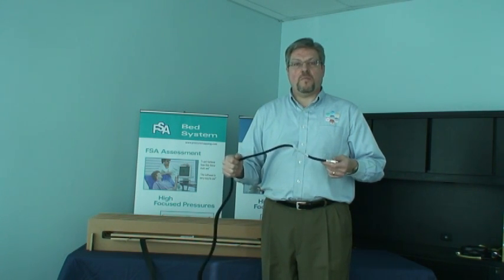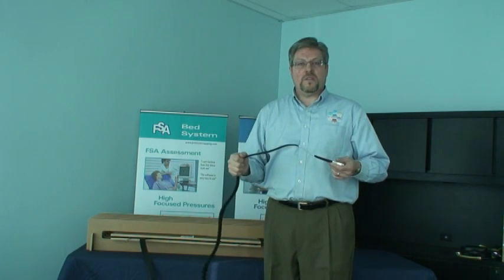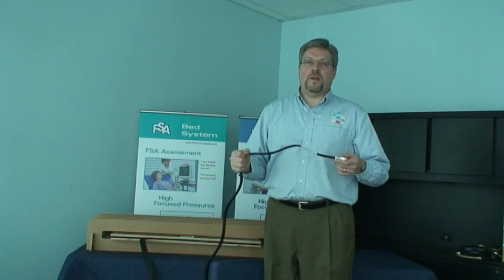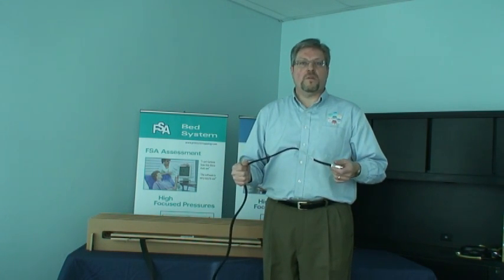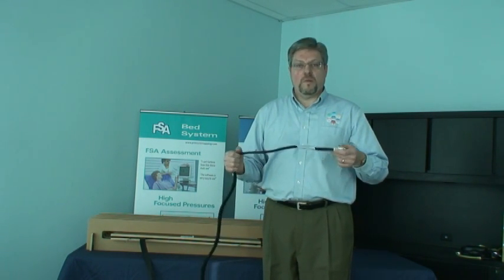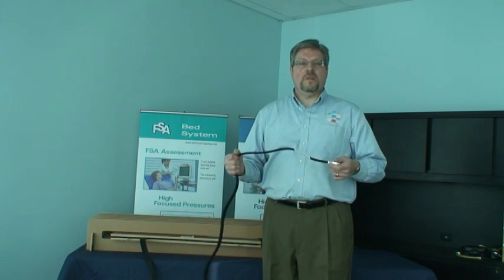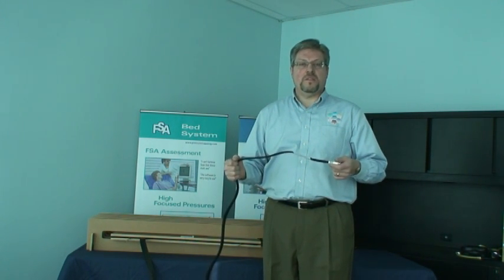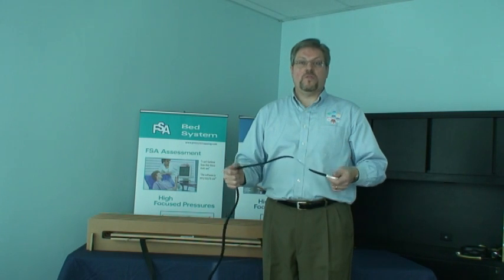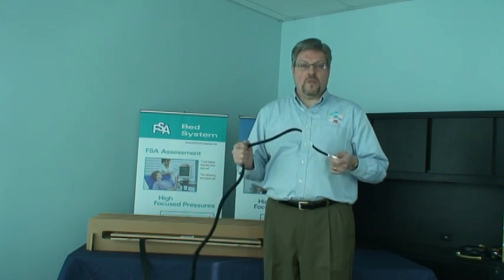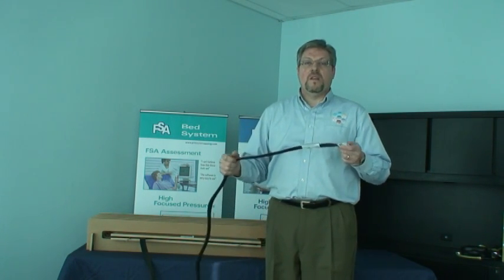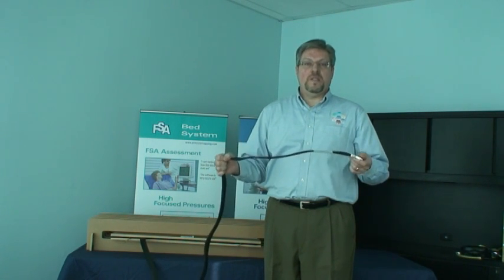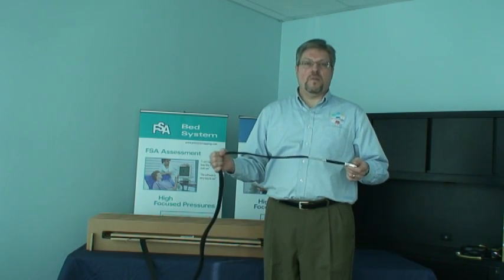It's going to take you through the process of pumping up and then deflating several times. Unless you have shop air, which means a compressor or an air reservoir, it's best to probably have two people, one person pumping while the other person is watching the screen, following the instructions and watching the sphygmomanometer. So when it says pressurize to 80 millimeters of mercury, they're watching the sphygmomanometer. When you hit 80 millimeters, you click on it precisely at 80 millimeters. The biggest variable in calibration is the operator, or the operators involved.